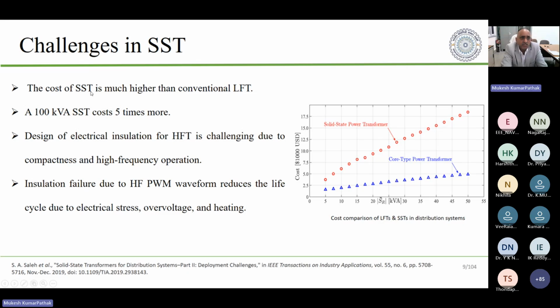As I said, the cost of the SST is much higher than the conventional transformer, you can see here. As the kVA rating goes up, the cost will also go up, and the gap between the cost of the solid state transformer and the conventional transformer grows with the rating. On the contrary, someone may think that as the power rating of the solid state transformer is increased, the gap should reduce, but this gap is increasing. So this is also a real problem. So, the efficiency and the cost. Now, a 100 kVA SST costs nearly 5 times the conventional transformer.